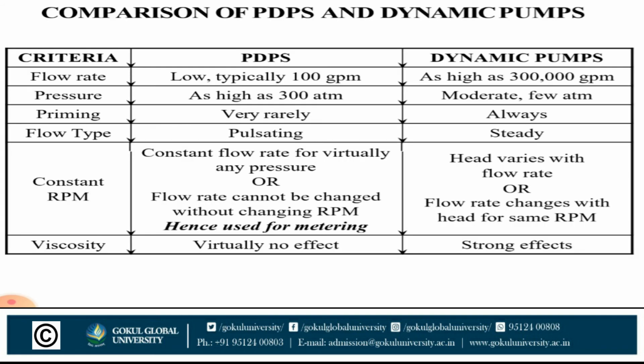Comparison of positive displacement pump and dynamic pump. Flow rate: positive displacement pumps are typically around 100 GPM, and dynamic pump flow rate is high, up to 3 lakh GPM. Pressure of PDPs is high, 300 atm. Dynamic pump pressure is moderate, a few atmospheres. Priming of positive displacement pumps is very rarely needed, and for dynamic pumps priming is always needed. Flow type of PDPs is pulsing, and dynamic pumps is steady. At constant RPM, PDPs give constant flow rate regardless of pressure, and for dynamic pumps head varies with flow rate. And last, viscosity has virtually no effect on PDPs and a strong effect on dynamic pumps.